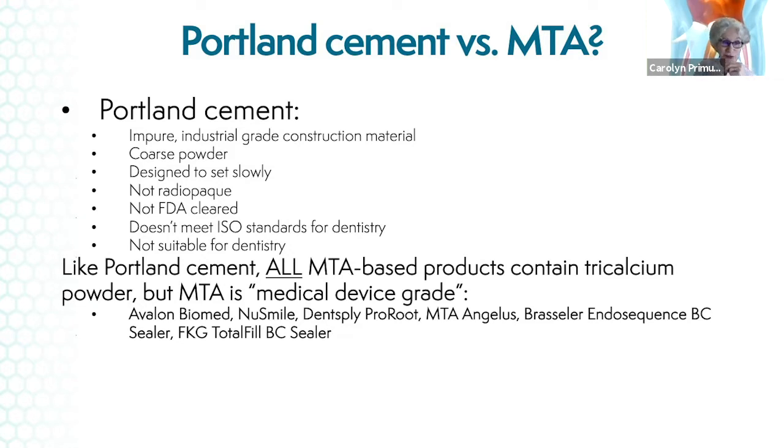Portland cement for construction is designed to set slowly so you can mix it and take it to a construction site and use it there for pouring. It's not radiopaque, it's not FDA cleared, it doesn't meet the ISO standards for dentistry, so it's really not suitable. However, chemically, all the MTA-based products do contain the same chemical that's used in Portland cement, but really manufacturers are using a medical grade device. And that's true for all the products that I've listed down at the bottom.